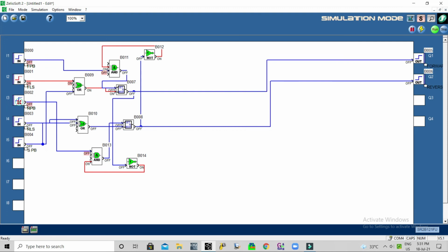Now you press the reverse push button, reverse is running, the forward limit switch is reset, and once it reaches the reverse limit, the limit switch is activated. So this is how the logic works with the interlock system as well as the push buttons. We will test the stop button also. Okay, stop. So this is how we can provide interlock for forward and reverse in this logic.